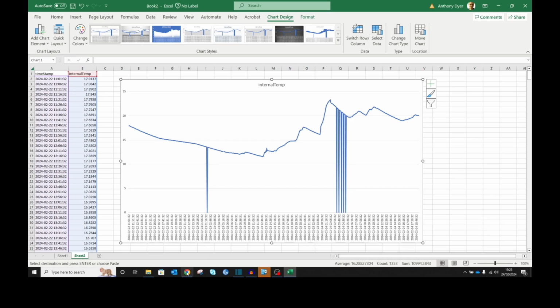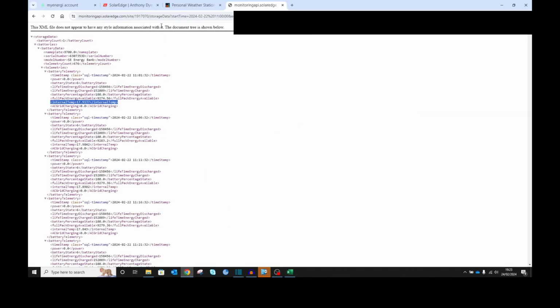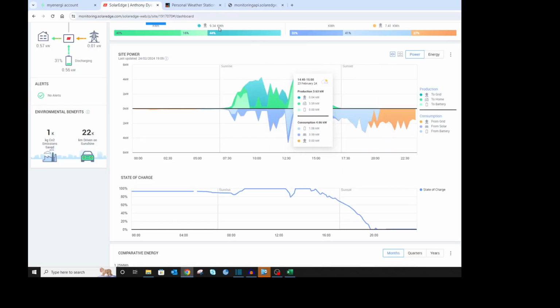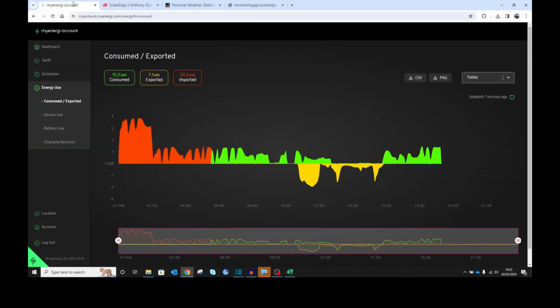In terms of that variability, there isn't too much information here, but if you go on to myenergi, this has a 5-minute resolution so you get much stronger data - you can see these troughs. The heat pump's turning off every 30 minutes roughly, and I don't think that's a defrost cycle. My expectation of heat pumps is that they should run continuously, with the exception of defrosting, and what we're seeing here is quite regular cycling going on.